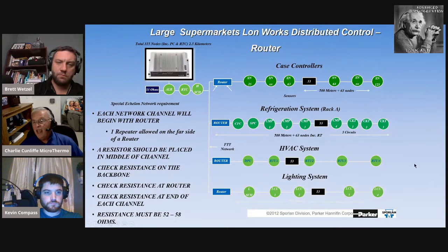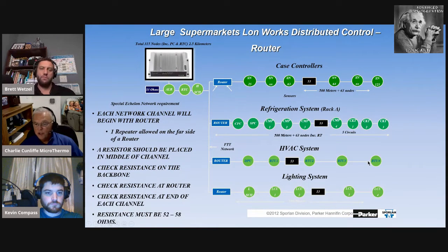If you were on the HVAC system upstairs and you got to the end of RTU4 and it was 84 ohms, I'll guarantee you're going to have a problem with that channel. They either used too much wire, did one big daisy chain on the channel instead of a star to cut down cable, or they did a bunch of courtesy loops or double backs. Again, everything should be as close to 53 as possible.